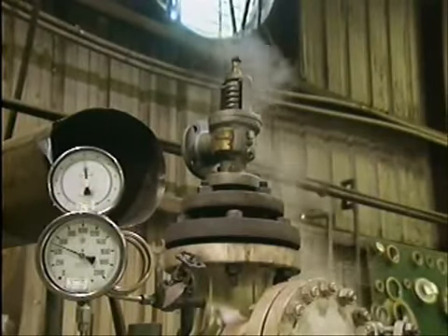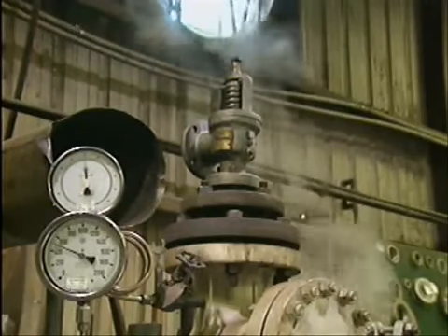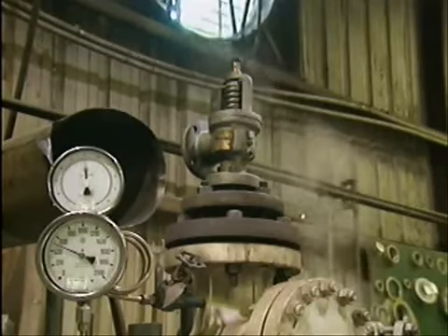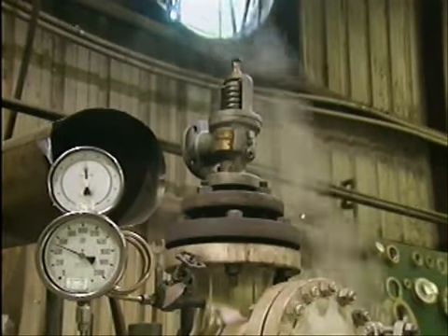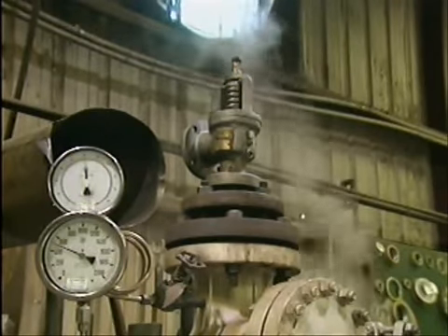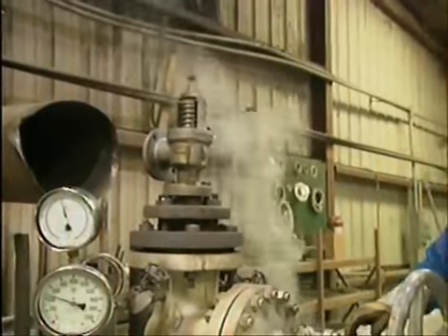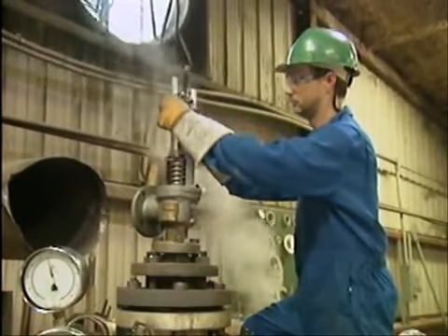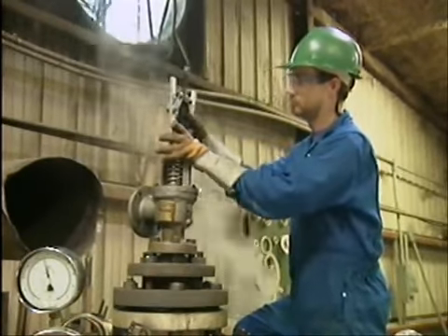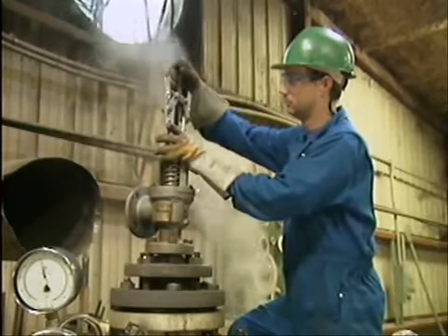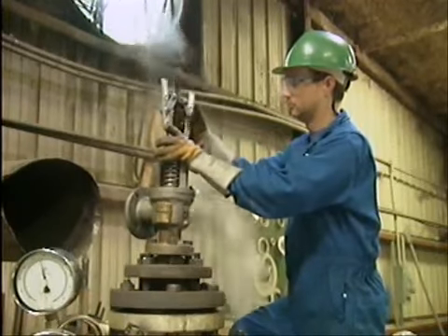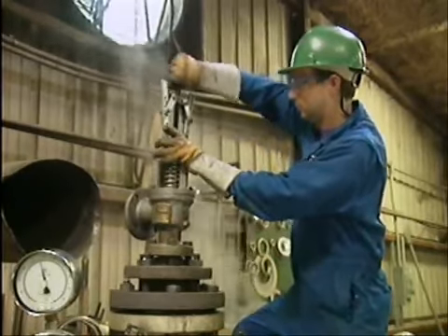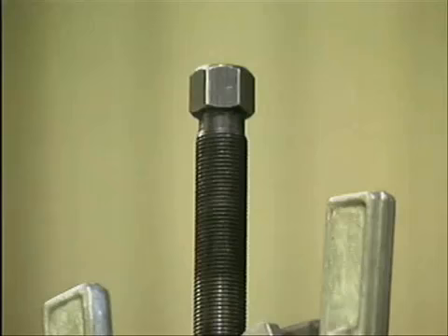We'll look at a typical procedure for installing a gag on a 2-ring huddling chamber safety valve. The valve's release lever and the protective cap have been removed so the top of the valve stem is exposed. Now, align the stem of the gag properly with the valve stem. Then, attach the jaws of the gag firmly to the yoke to prevent the gag from slipping. Finally, tighten the gag finger tight only. Never use a wrench on a gag.